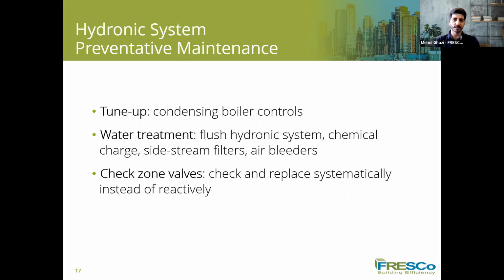So most condensing boilers are initially set up to a constant high temperature, ignoring the efficiency, which is not paying attention to the goal of installing condensing boilers. Even if they are set up to reduce temperature in warm weather, a typical pattern is that a technician reacts to the first cold complaint by overriding the system. So the control doesn't work in the way that it needs to work. This is something that we need to make sure of.